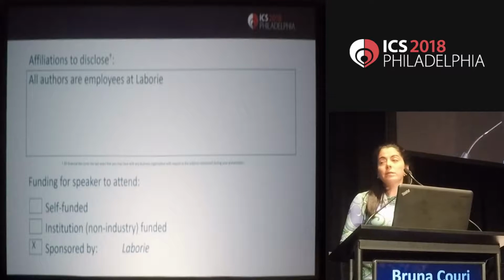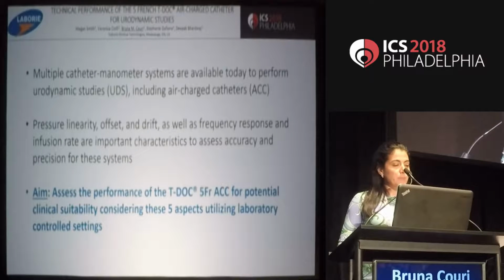All authors are employees at Laborie. Nowadays, multiple catheter manometer systems are available to perform urodynamic studies, including air charge catheters. Pressure linearity, pressure offset, pressure drift, as well as frequency response and infusion rate are important characteristics to assess accuracy and precision for these systems. The aim of this study was to assess the performance of the TDOC 5-French air charge catheter for potential clinical suitability considering these 5 aspects utilizing laboratory-controlled settings.